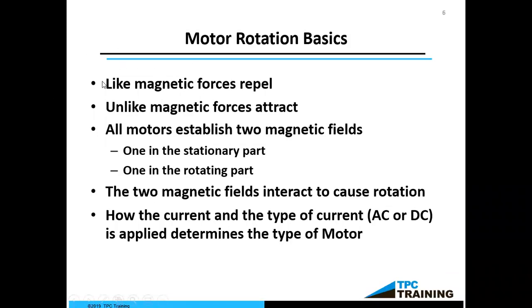If we go back in time, the Greeks discovered that like magnetic forces will repel, unlike will attract. That's what gives us our rotation: we establish two magnetic fields, one in the stationary part, which is going to be our stator windings, and the other in the rotating part, which is going to be our rotor. These two magnetic fields are going to be opposite in polarity, so they're going to attract each other, but it's also rotating 360 degrees, so it's going to bring that rotor right with it and cause that spinning sensation that we have.